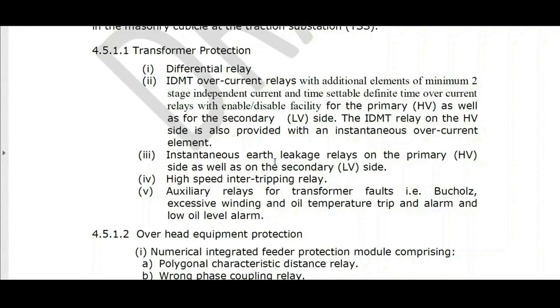The third protection is earth fault, instantaneous earth leakage system on HV and LV. So on the high voltage side as well as the low voltage side, if there is an earth fault, current flowing to the ground can also be detected. This again is non-unit because this doesn't pertain to any specific area. If you restrict it to a specific transformer alone, that is, if the earth fault occurs inside the transformer, it is called restricted earth fault. That means restricted earth fault is a unit protection. Earth fault is non-unit protection. So here we are just saying instantaneous earth fault. That means it is a non-unit protection.